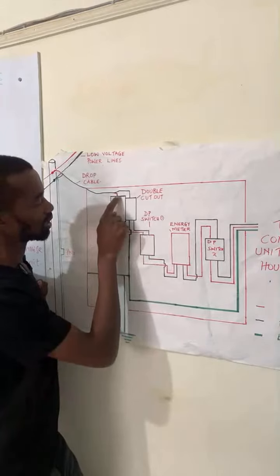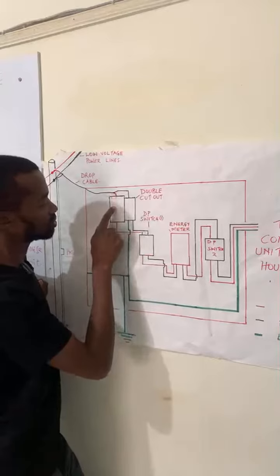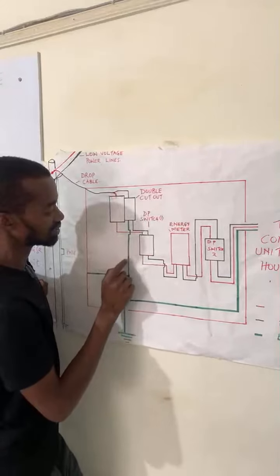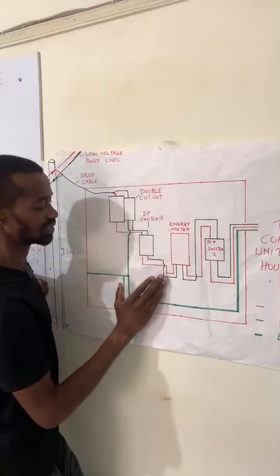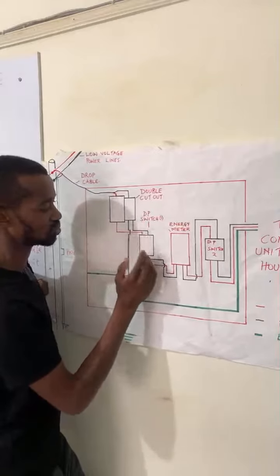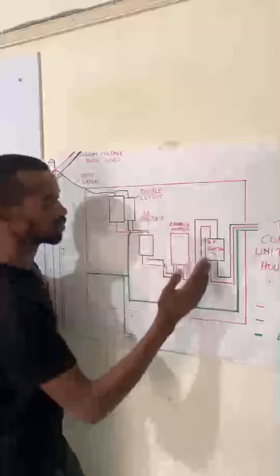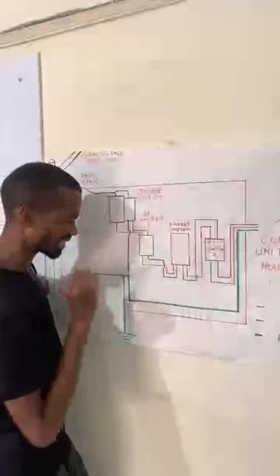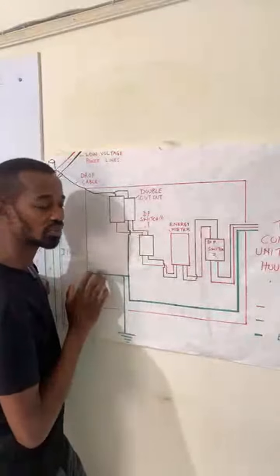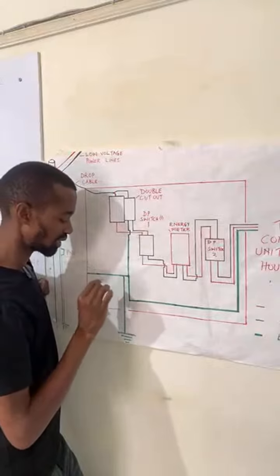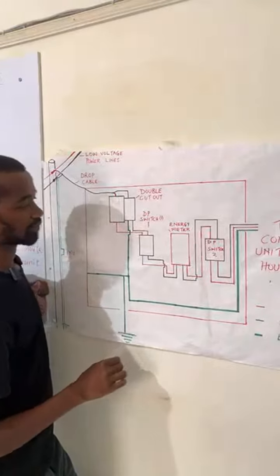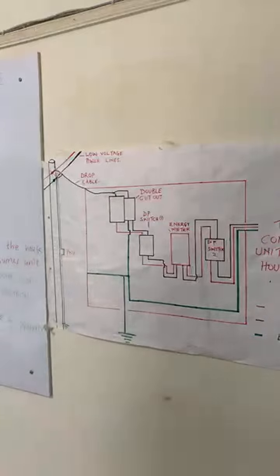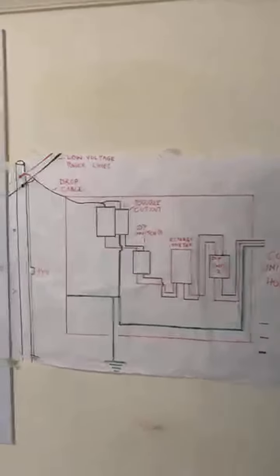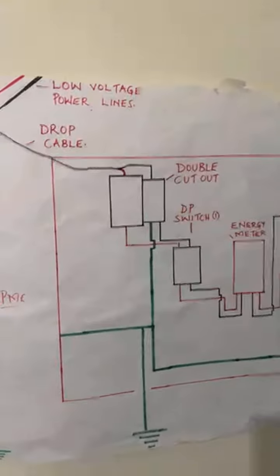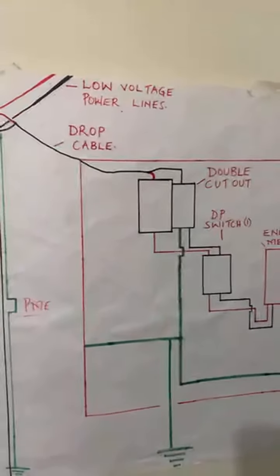talking about this connection. So the phase will drop at this point, and then exit, and it will go through the various safety devices, let's say a DP switch, all the way to the meter, all the way to another DP switch, or if you're using only one, and then to the consumer unit. But the earthing has to be bonded with the meter box as well as connected all the way to the earth rod. Yeah, so let me just give you a closer look at what we are talking about here, so that you may get a clearer picture, my top boss.